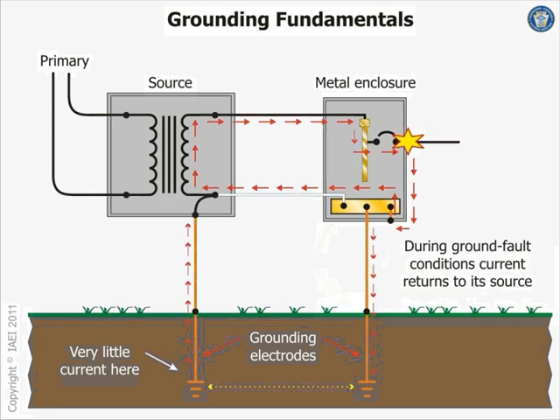So here's a ground fault here. 99% of the ground fault, if not more, will have a free ride over the Interstate 494 here. The other 1% or less will go to the alleys of Minneapolis. You know, because it's really high impedance here, and you might find a lot of kids working in the alleys and so forth. So you go to the high impedance. Any comments? Any questions, guys? Yes. Yes, sir. Chad, I wasn't sure if you were going to mention this earlier. It got my attention that earlier you talked a little bit about protection from lightning.